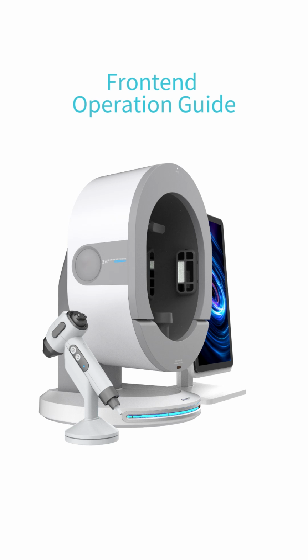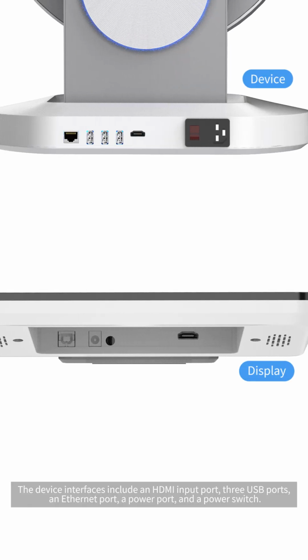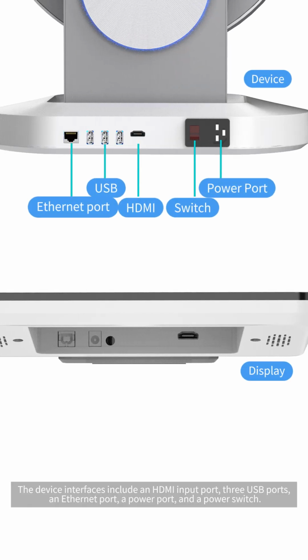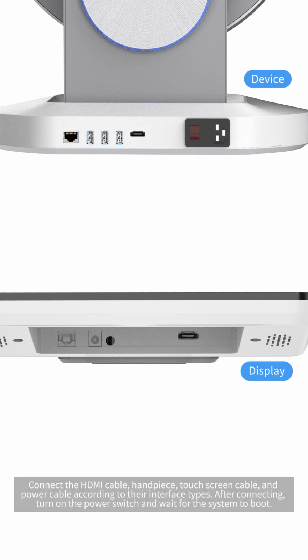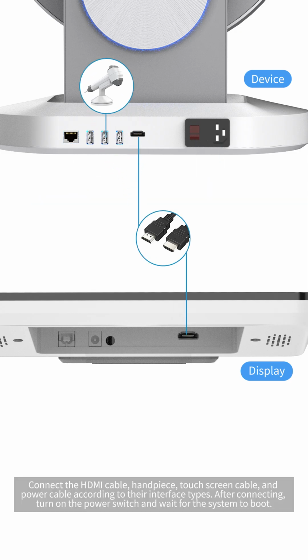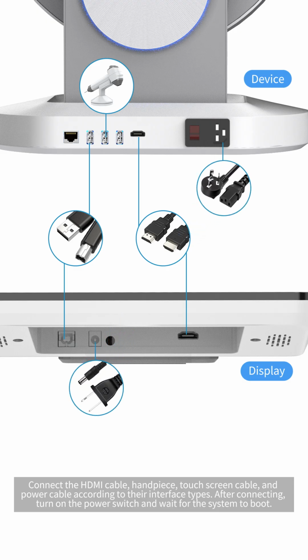Front-end operation guide. 1. Power on. The device interfaces include an HDMI input port, 3 USB ports, an Ethernet port, a power port, and a power switch. Connect the HDMI cable, handpiece, touchscreen cable, and power cable according to their interface types. After connecting, turn on the power switch and wait for the system to boot.